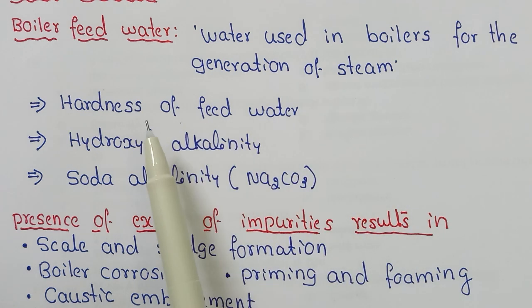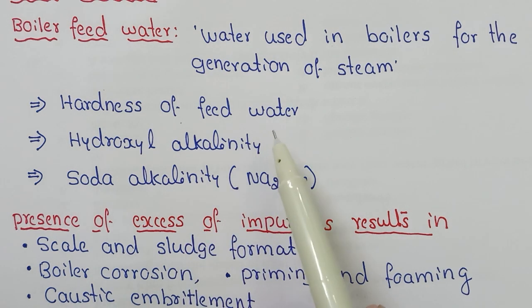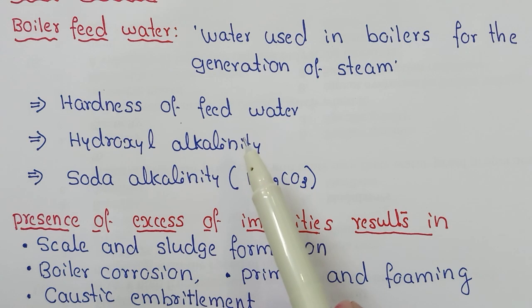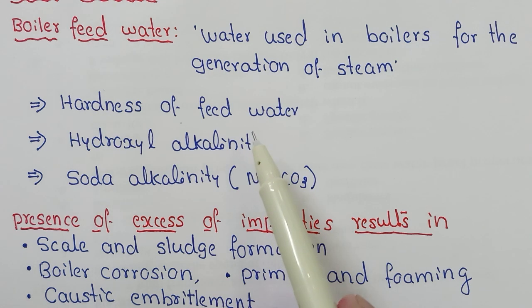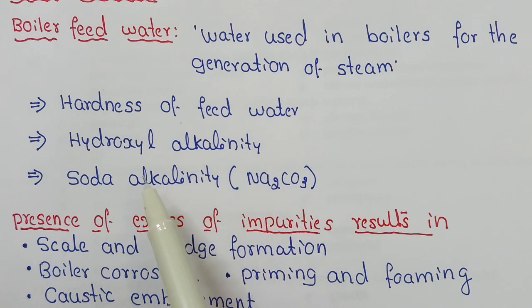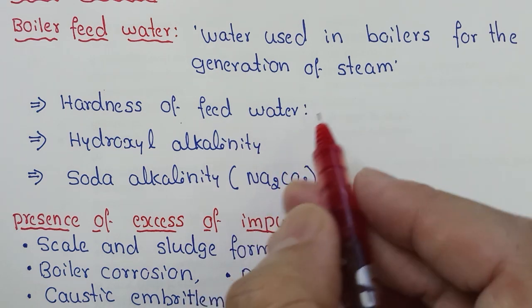The water fed to the boiler contains many impurities. It is necessary to eliminate the impurities that cause serious operational troubles in boilers before supplying water into them. Boiler feed water should contain the following parameters within limits: hardness of feed water, hydroxyl alkalinity, and soda alkalinity. Hardness means the property of water to resist lather formation — hard water does not give lather with soap.